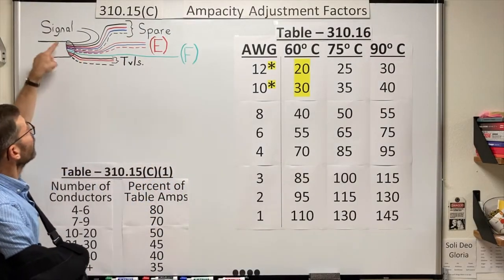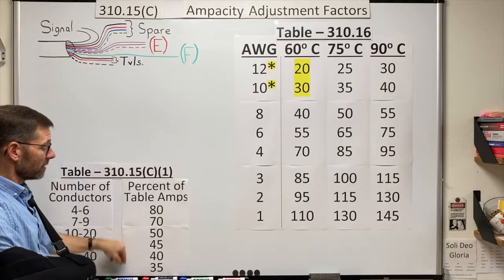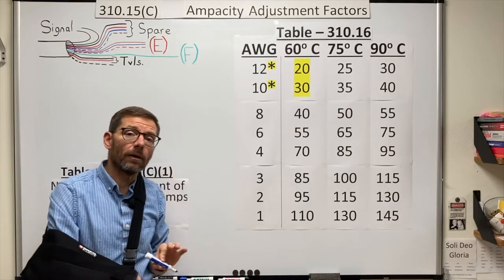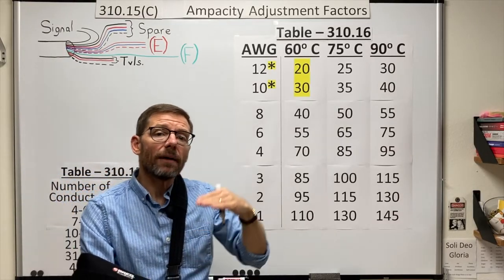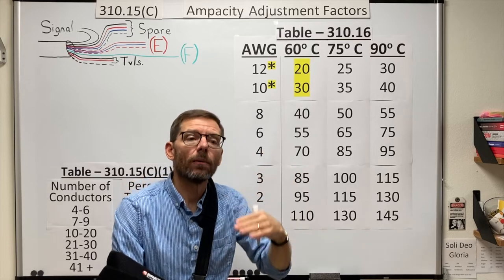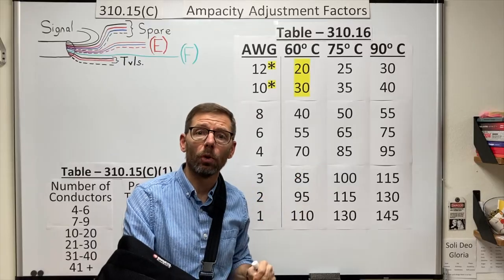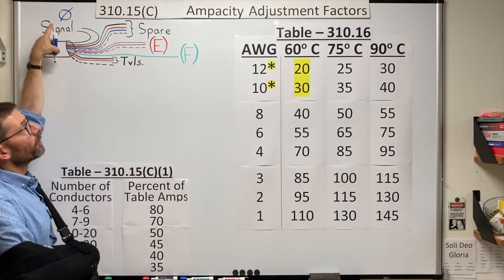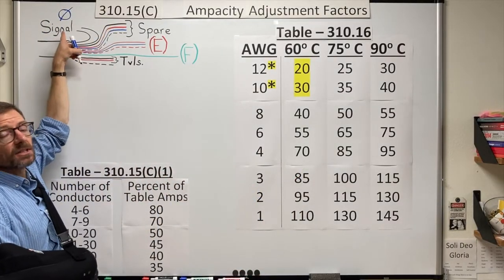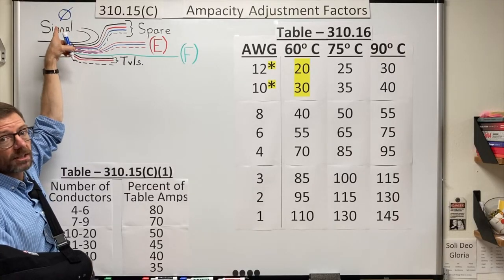In my diagram, I drew some signal conductors. They would not need to be counted because they don't have an appreciable current. They wouldn't be adding heat. They're just sending a signal back and forward or maybe some small controls. So for this calculation, the signal or control wires would not count.